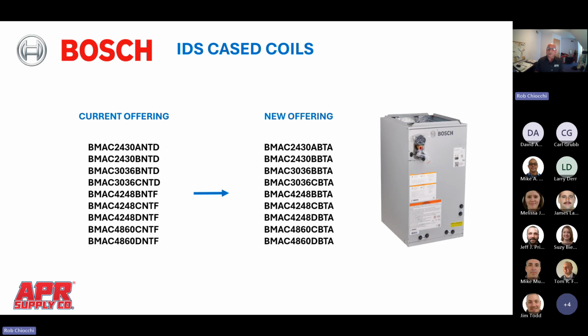Same with the coils. The coils aren't going to change. They'll still be available as a multi-poise coil in dual rated sizes in the standard cabinet widths. The only real difference you will see with the coils as compared to the R410A coil is the extreme amount of warning stickers talking about the R454B A2L flammable refrigerant incorporated within the system. These labels are all mandated now by the EPA, and they're pretty large and encompass the front of the coil, but that's the only physical difference you'll actually see with the coil.